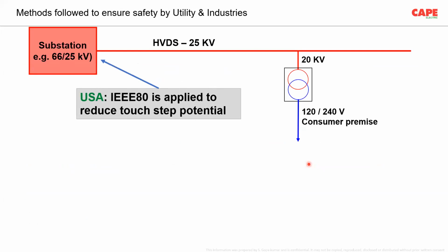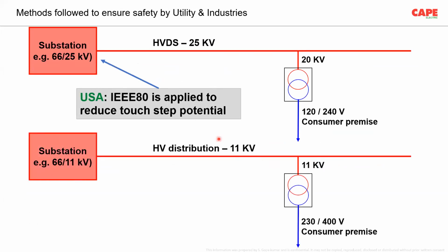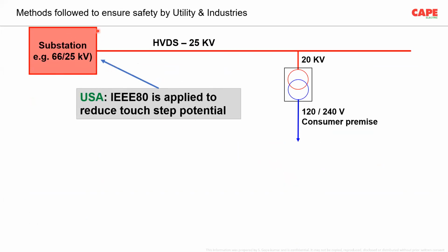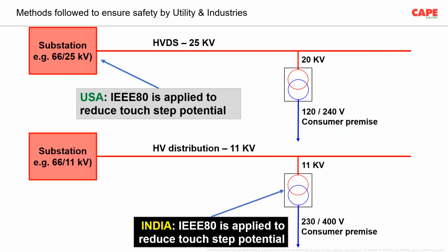So what conclusion from this is, in America, they have the substation, and the IEEE 80 is used in the substation, 66 kV/25 kV, for example. The touch and step voltage reductions are made there. Whereas when it comes to India, we use the same principles for a 11 kV or a 230 volt transformer. This is actually wrong. We are supposed to use it here at a substation, a transmission or a distribution substation.